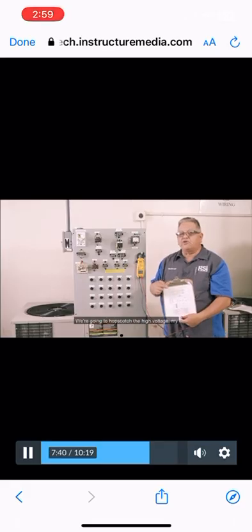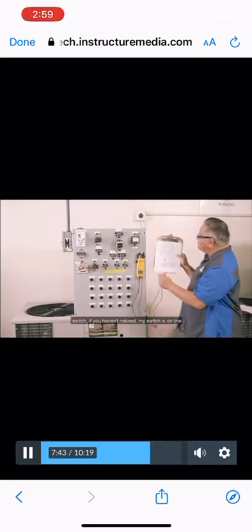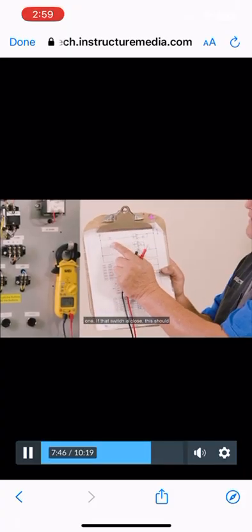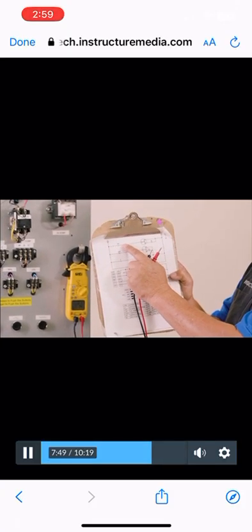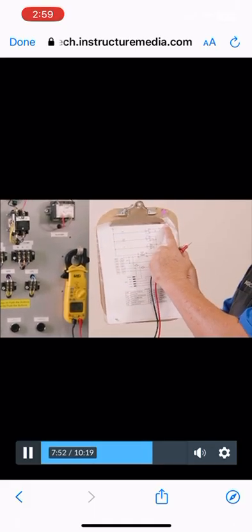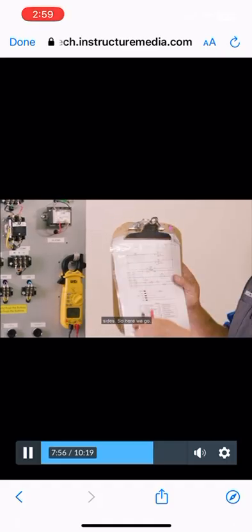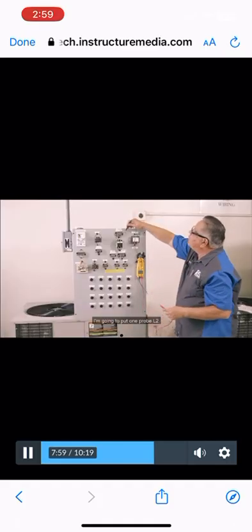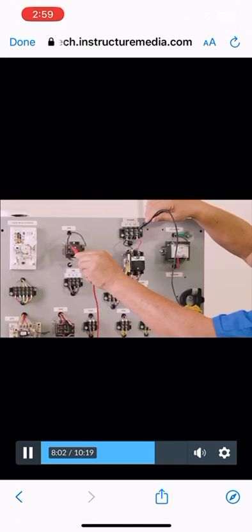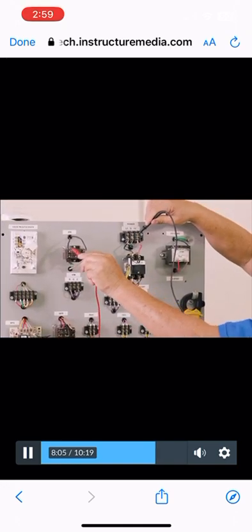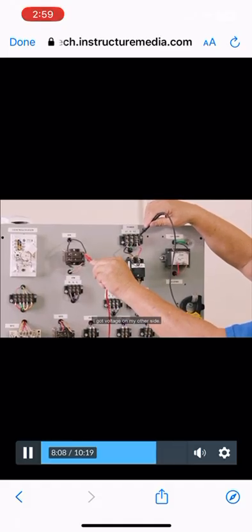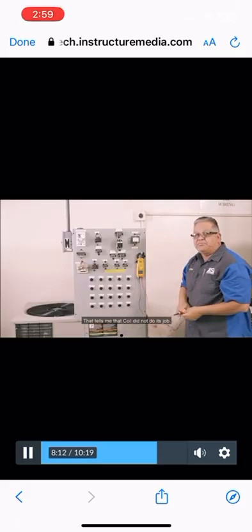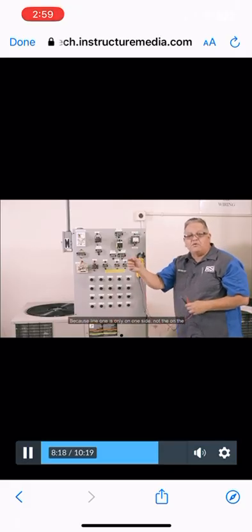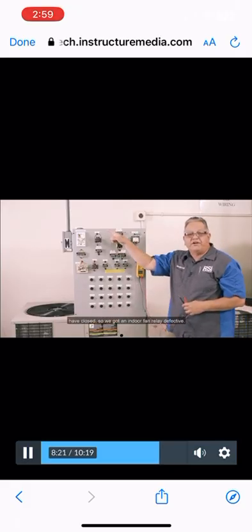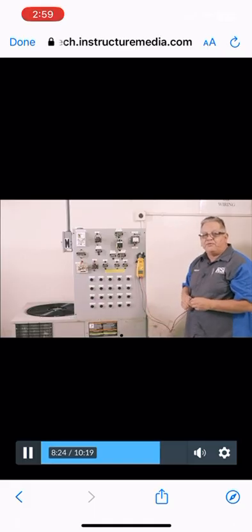Okay, so this is what we're going to do. We're going to hopscotch the high voltage. My switch, if you haven't noticed, my switch is on line 1. If that switch is closed, this should all be line 1. I'm going to put one probe on L2. If that switch is closed, I should read voltage on both sides. So here we go. I'm going to put one probe on L2. I'm going to go across the switch. I got nothing on one side. I got voltage on my other side. That tells me that coil did not do its job. It didn't close the switch, because line 1's only on one side, nothing on the other. And because I'm reading 24, it should have closed. So we got an indoor fan relay defective.